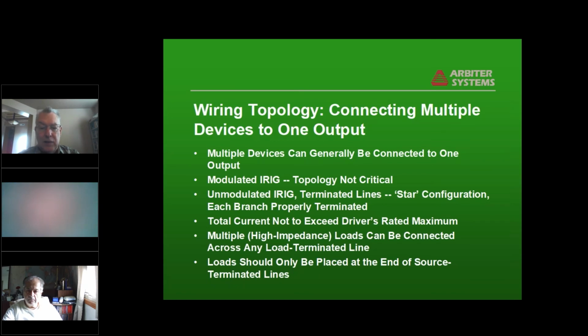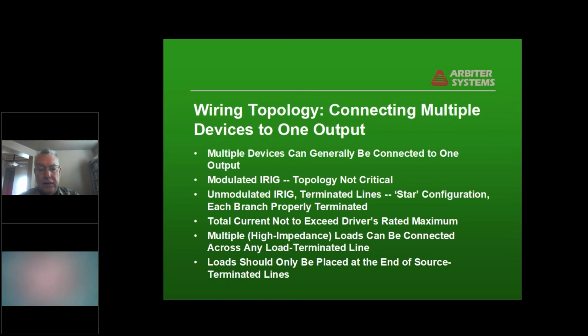Unmodulated IRIG has fast transmission edges. You need to have terminated lines. If you have a star configuration with each branch properly terminated, you can do that. Remembering that each load with each line that has a 50 ohm load at the end is going to draw 100 milliamps. So if you have 200 milliamp current capability, you can put a star configuration with two loads.